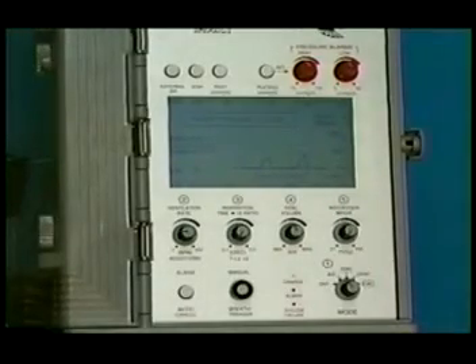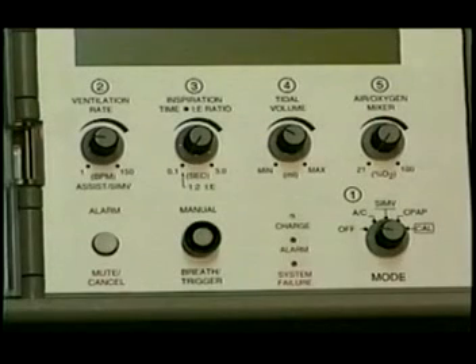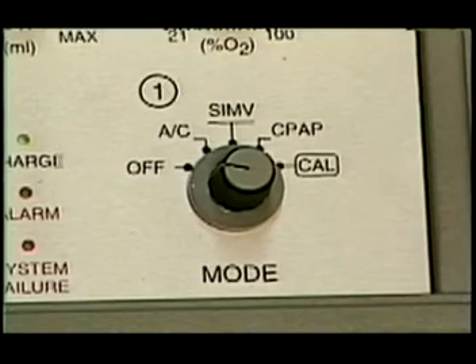Let's take a look at the ventilator's front panel and review its controls, their functions, and its indicators. The first set of controls we'll discuss are the primary controls. They're numbered 1 through 5 on the panel and determine the operating mode, its characteristics, and percentage of oxygen delivered. The mode selector switch is the control numbered 1. It applies operating power to the ventilator for assist control, AC, synchronized intermittent mandatory ventilation, SIMV, continuous positive airway pressure, CPAP, or transducer calibration, CAL.